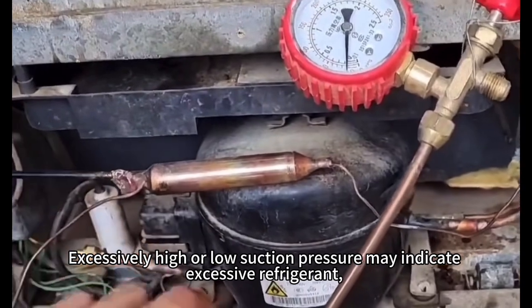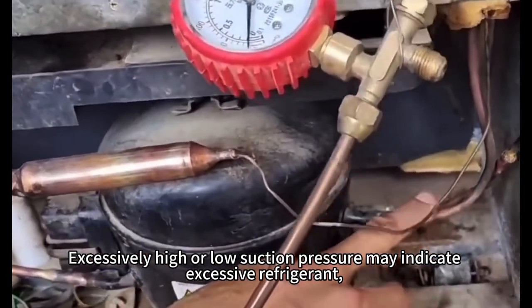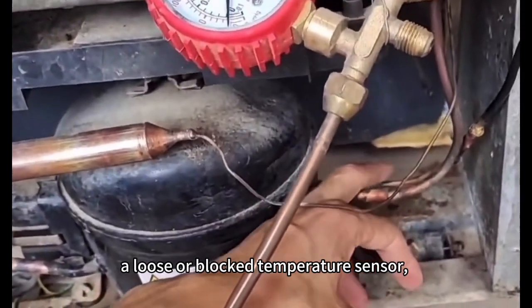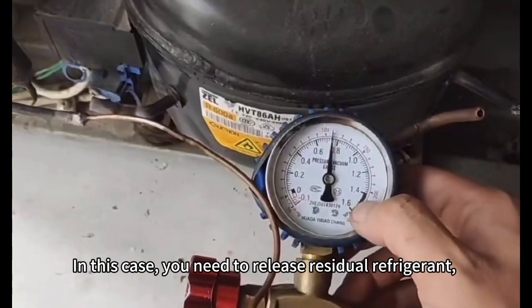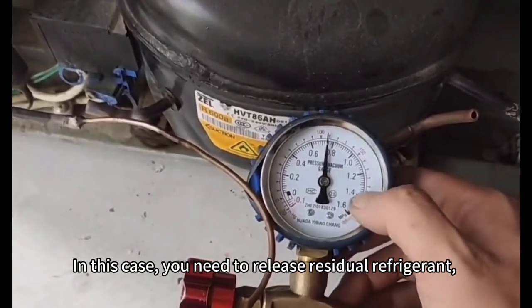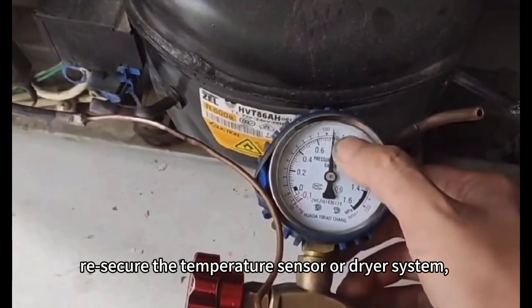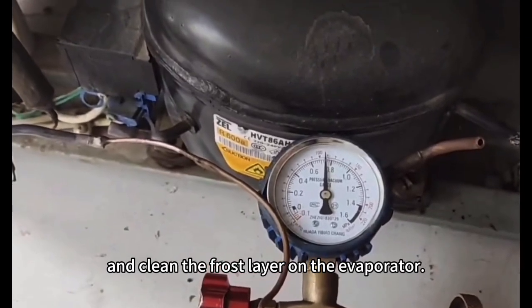Excessively high or low suction pressure may indicate excessive refrigerant, a loose or blocked temperature sensor, or frost buildup on the evaporator. In this case, you need to release residual refrigerant, resecure the temperature sensor or dryer system, and clean the frost layer on the evaporator.